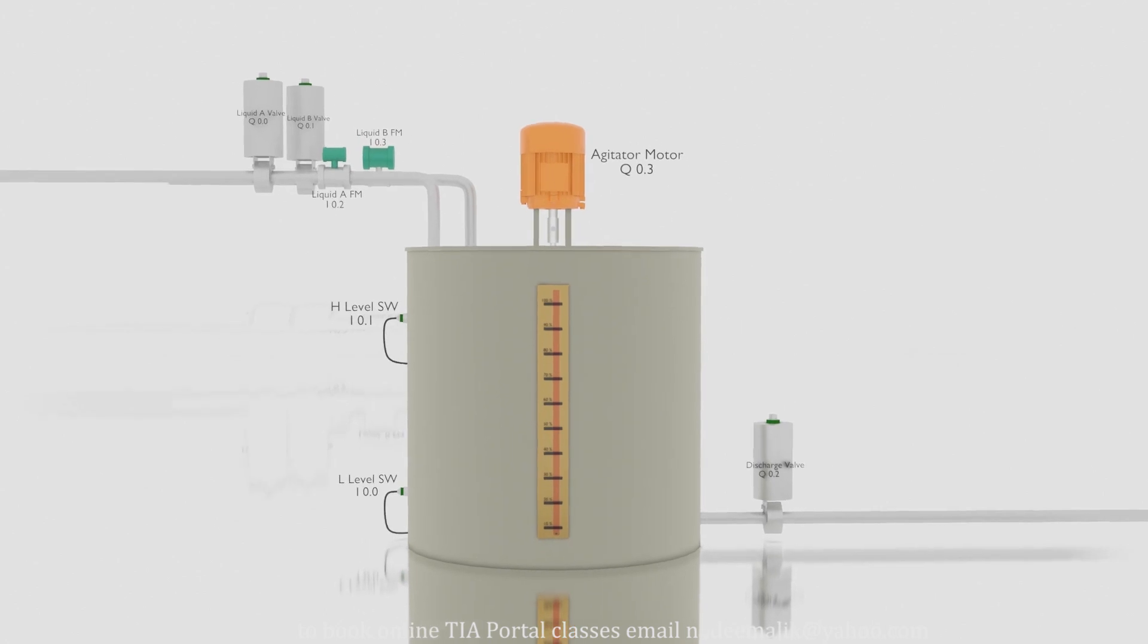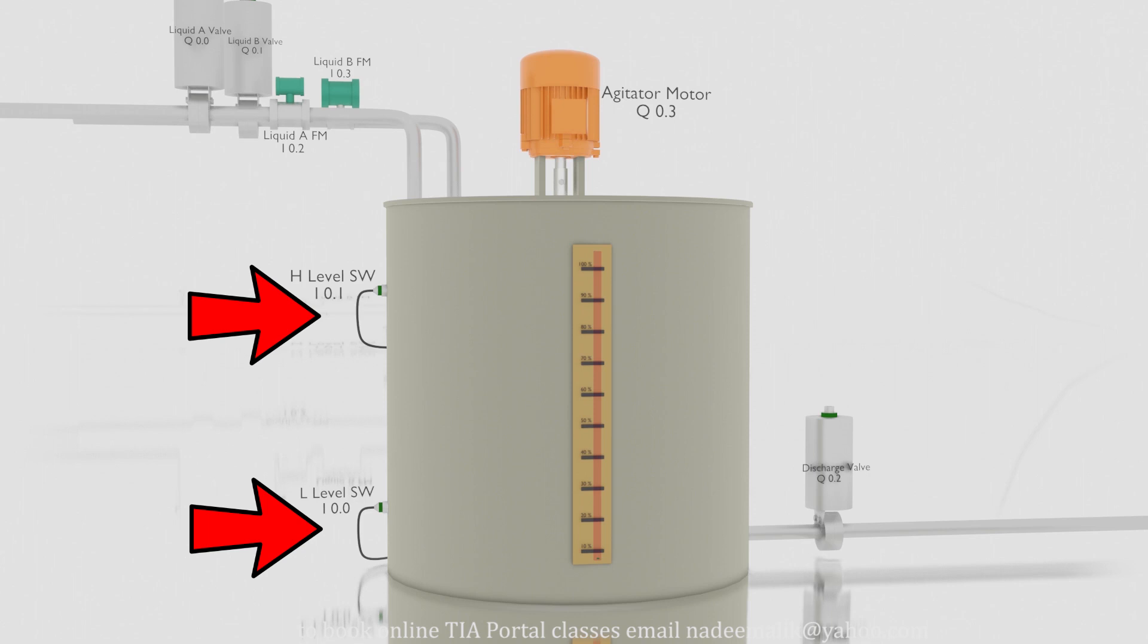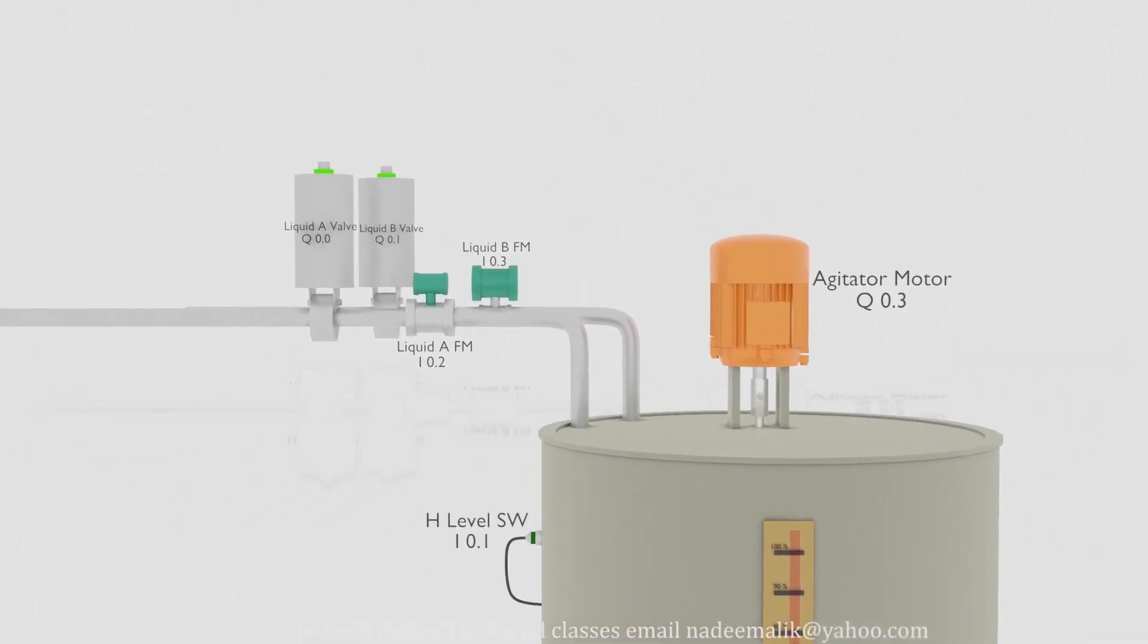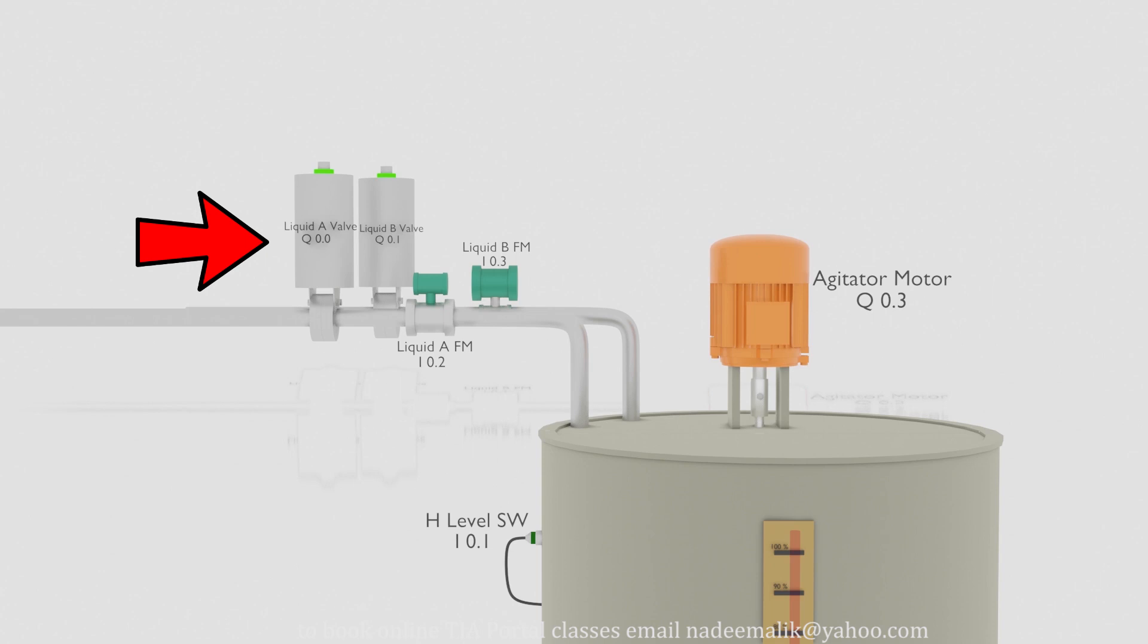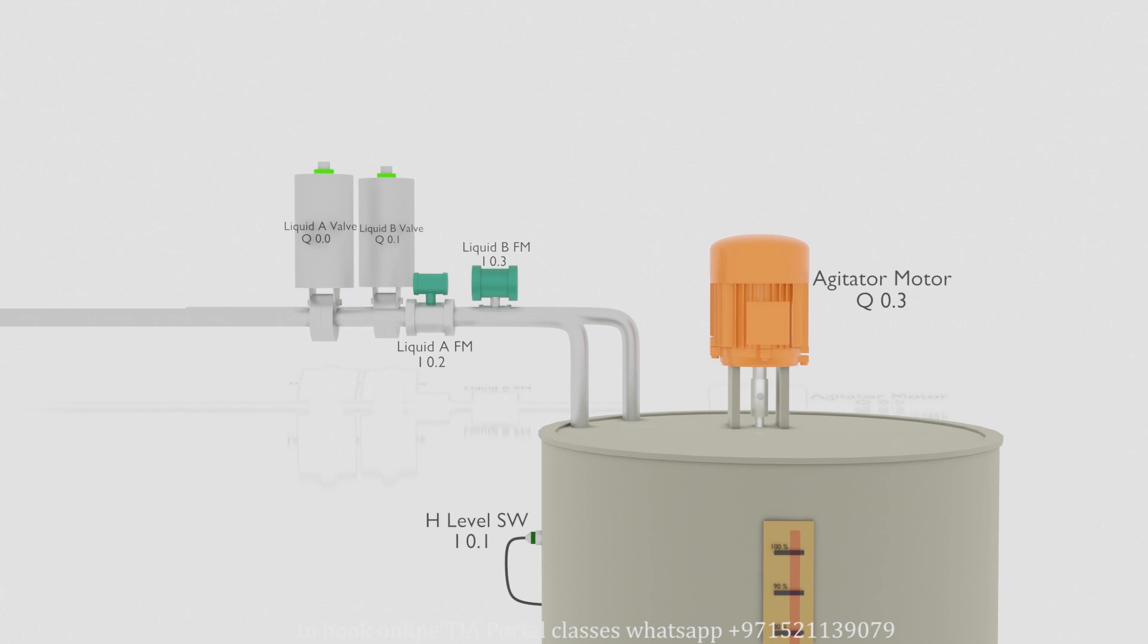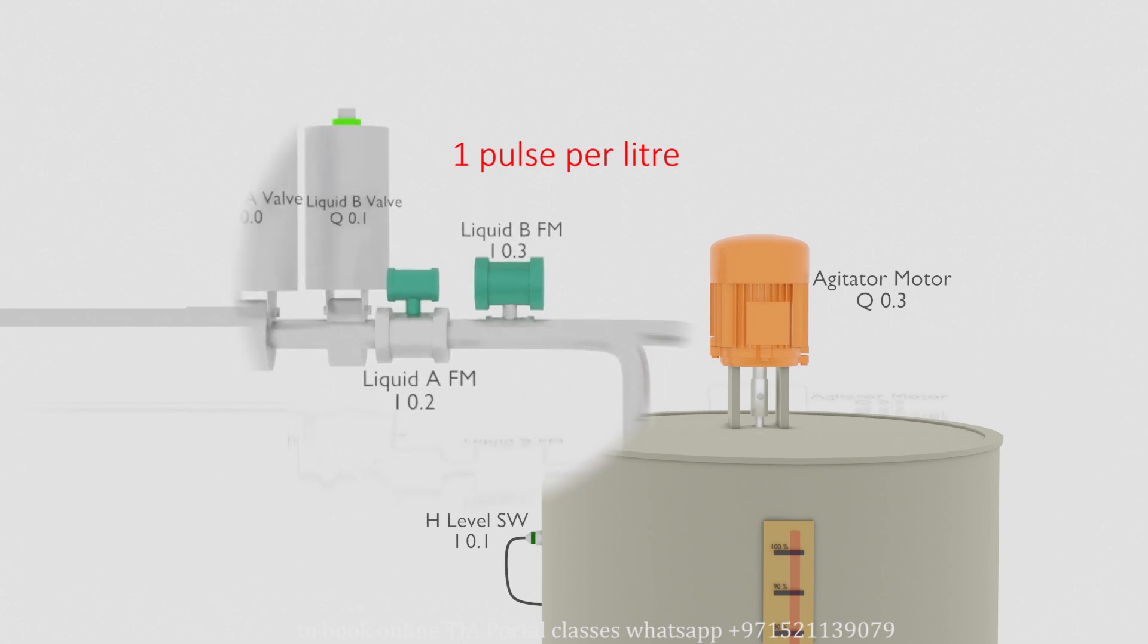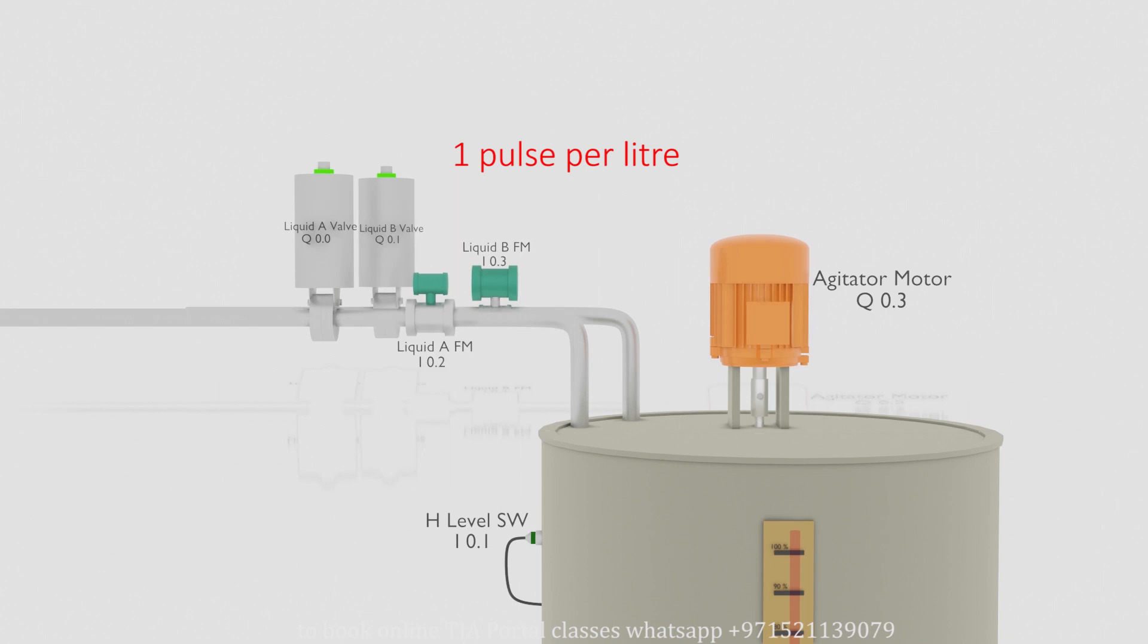Firstly we have a tank with a low level probe I0.0 and a high level probe I0.1. Next we have two inlet actuator valves operated by the PLC outputs Q0.0 and Q0.1. These valves are used to fill the liquid in the tank. We will first pour 50 liters of the liquid from both valves A and B. We can measure the liters using the flow meters installed on each line. These flow meters output a pulse per liter of the liquid on the PLC inputs I0.2 and I0.3.